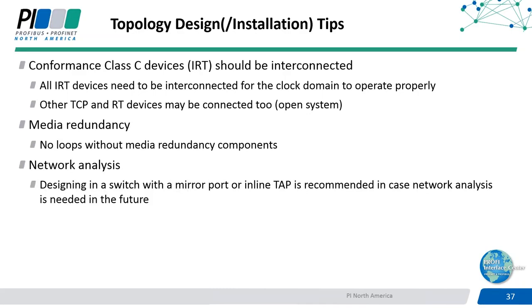Regarding network analysis, since we're doing a lot of switched Ethernet with PROFINET, the switches basically forward the traffic between the devices using the Ethernet MAC addresses. So if you try to plug your PC in to capture traffic for diagnostic or performance reasons, you can't do that with just a straight connection. You have to have a switch with a mirror port or a network tap to copy that traffic from the controller to the devices, and then you can view it with an Ethernet sniffer or network diagnosis tool. These test tools are available from multiple suppliers and are also often a feature on a managed switch supporting PROFINET too. So if you're looking for that, you want to get that.